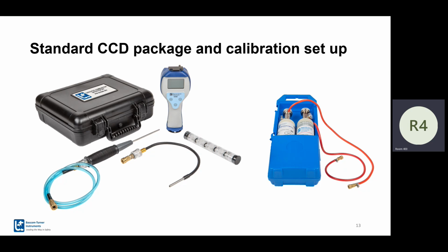I have done intensive drift testing, basically seeing how the same gas I measure over and over for 8 hours. I've not done it in the field. In the lab, we have never had one fail that plus or minus 10%. But take it with whatever grain you want because I can only test so many devices.